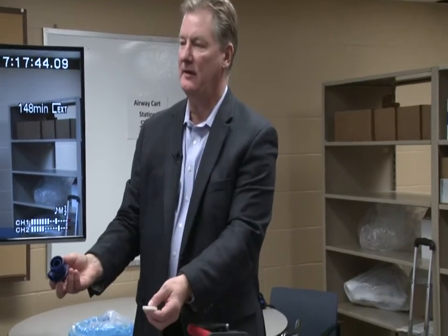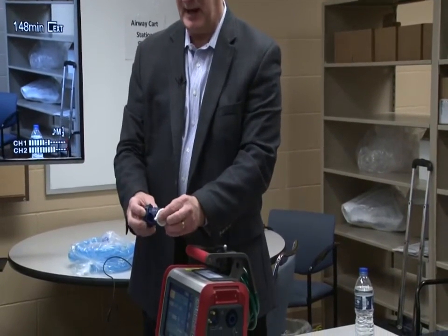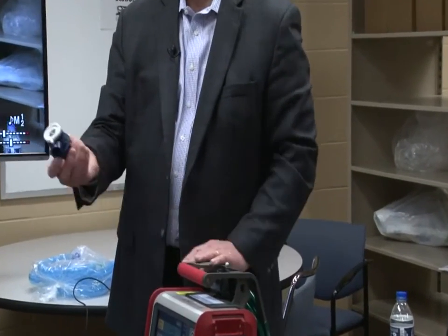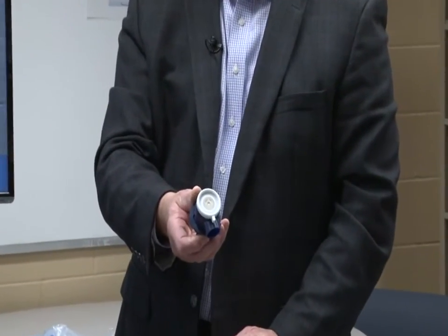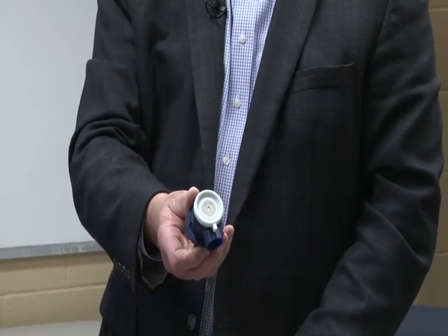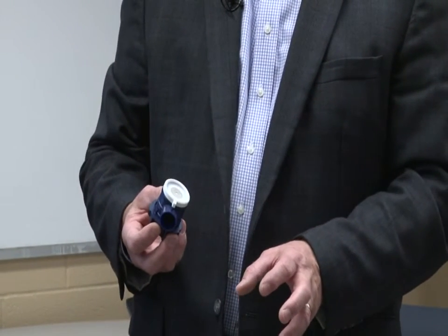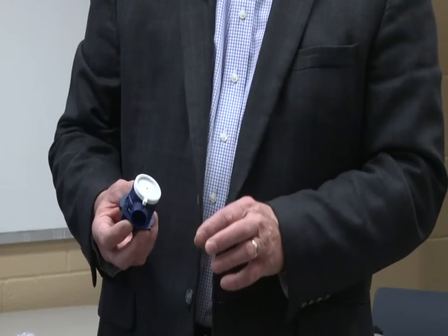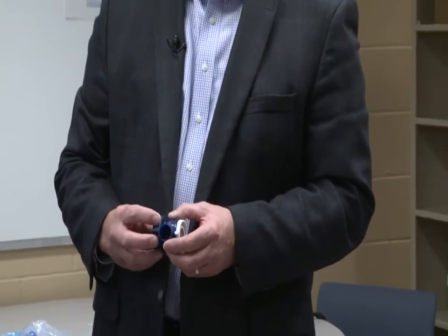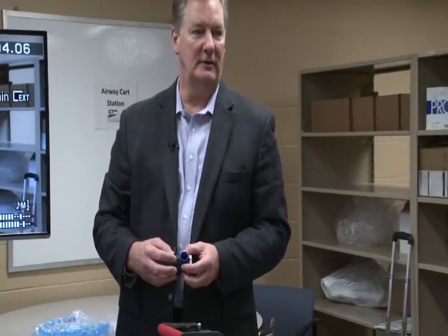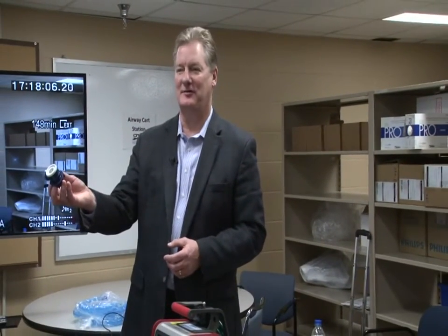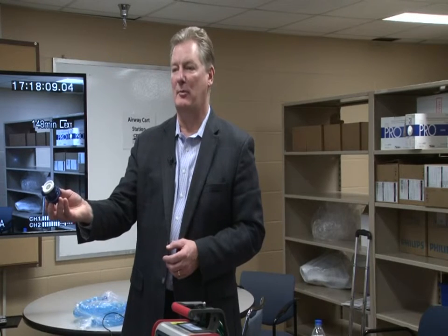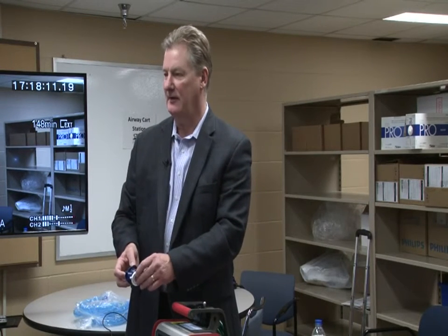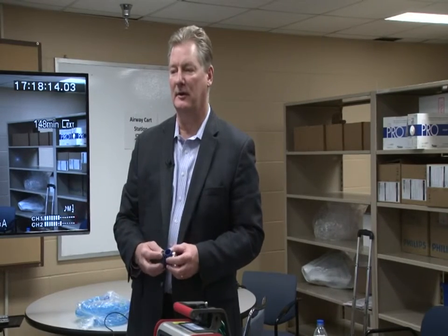So you notice there's a little notch on the diaphragm, and there's a little notch on the top of the housing as well. The easiest way, if you have to take it off or check it, is to put the notch over the little tab, and the rest of it just fits on there like a little cap. Okay? We're going to do a tightness test here in a minute, and we're going to do a flow sensor calibration. In any case, about 95% of the time, if you have a problem with either of those things, it's related to the fact that it's either got a hole in it or it's not on properly. Somebody put it on and the little tab is caught on the cup, or whatever the case might be.